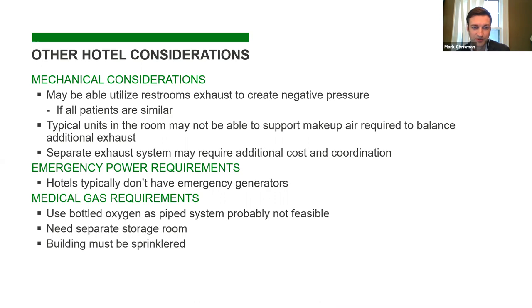Tied to the ventilator, basically all those patients are getting oxygen. It's probably not going to be feasible to install a piped medical gas system like we'd normally have in a hospital, where you've got oxygen, vacuum, and air all at a patient's bed. So they'd be running through bottled oxygen, probably in cylinders, and there's definitely concerns with that.